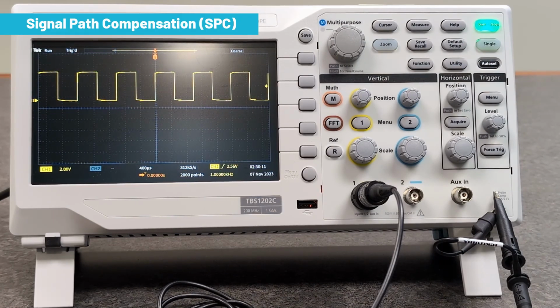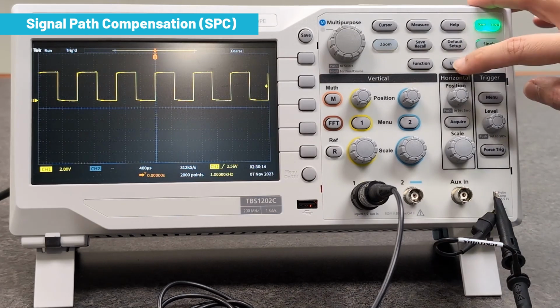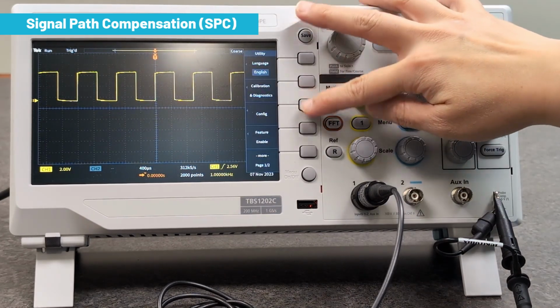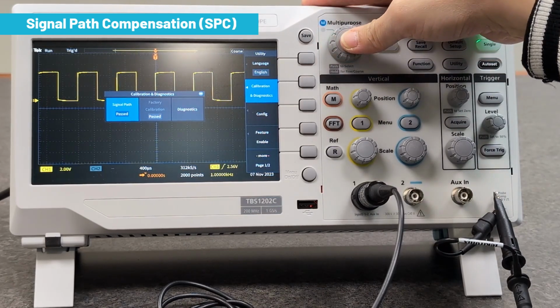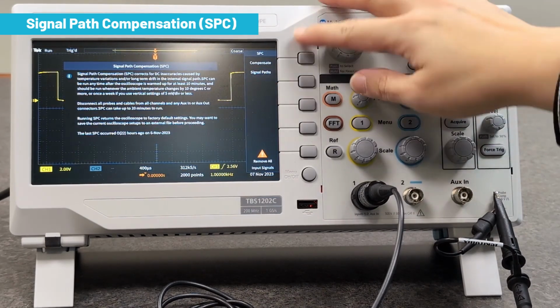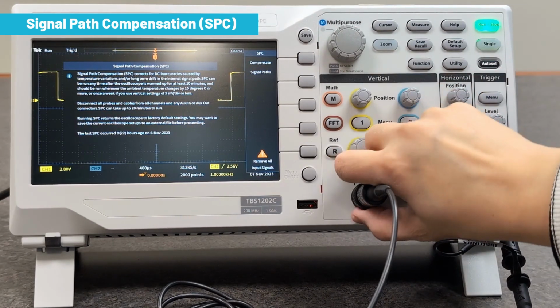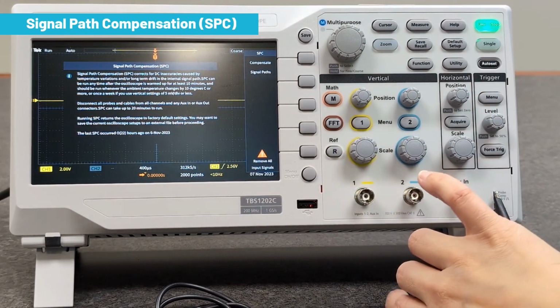Signal path compensation, also known as user calibration, helps correct DC inaccuracy. It is recommended to perform SPC on a weekly basis or before making any critical measurements. If SPC fails, there may be a hardware issue that requires your attention.